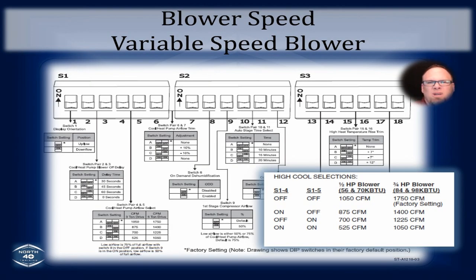Okay, here's an example of the manufacturer's diagrams on how to adjust the blower speed. If you look at the switch banks at the top, we've got switch banks 1, 2, and 3. And if you look at the cooling selections here on the little breakaway chart just off of the left-hand side of where I am, which is right over here, you'll see the cooling selections. And they tell you whichever size blower you've got, that's going to be the corresponding CFMs for your configuration of dip switches. Okay, so if you've got the 56,000 or the 70,000 BTU furnace, then you can have a half horse blower, and your configuration of switch bank 1, dip switch number 4 and dip switch number 5, both in the off position, will be 1,050 CFM.